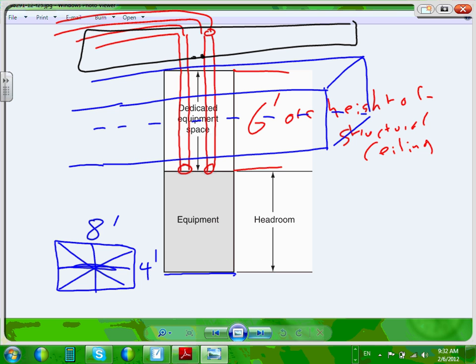For example, if I'm to put a water pipe right there, I wouldn't put any couplings right at the top, because if you have a water pipe not in the dedicated space above right here, and you have a coupling here, that could leak. But if you have just a big conduit, the length of the equipment, it's highly unlikely to leak, right? But you might have to get into an argument. So the rule is avoid putting anything even above that.